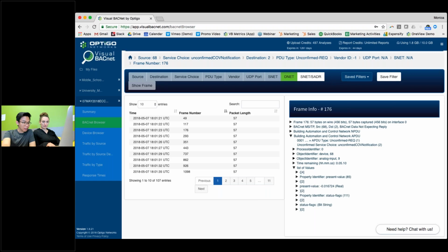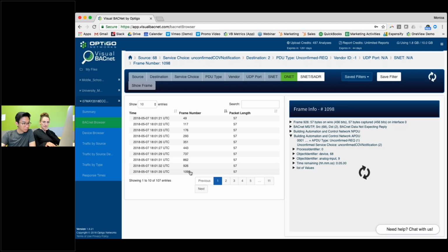So you want to look based on the specific device. One thing to note is that it may be on a COV for the analog input. One thing to note is what the read interval is. If you're on change of value, and your interval is set at, say, 0.1 or 0.01 increments, you're going to get a lot of traffic in a short period of time. So to reduce this, we could look at that interval and change it a little bit.